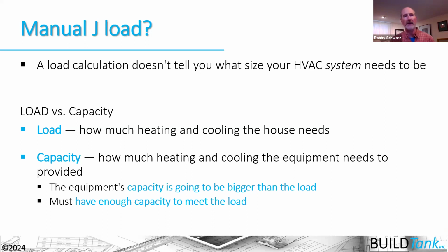Now, this becomes even more crucial when we start talking about heat pumps, and we're not going to go into depth with regards to heat pumps. But what we know with regards to an air source, or a ground source, well, really with an air source heat pump, is that as the temperature goes down, the capacity of the system goes down as well. Therefore, sometimes we need to size it bigger in cold climates to be able to get the capacity at that lower temperature. And we're going to pick systems specifically for our climate region throughout Colorado. We want to ensure that we're installing cold climate heat pumps in order to get a system that has greater capacity at low temperatures. And we need to right size them for our houses as well.